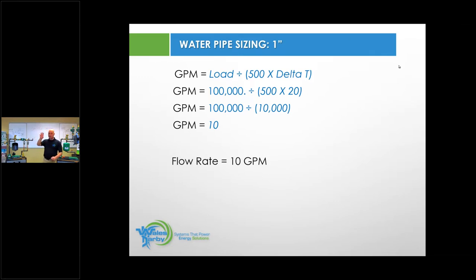I want to get the gears turning here, and I want everybody to understand we have to take that water that's in that boiler and distribute it to our heat circuits. We have to deliver the heat energy to those heat circuits, and then we have to bring it back, re-energize it, reheat it, and send it back out again.